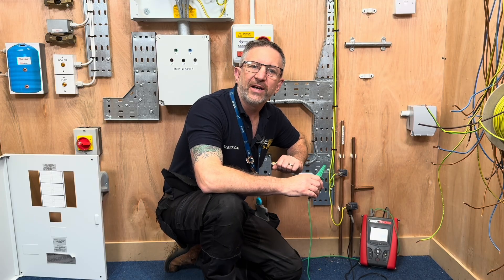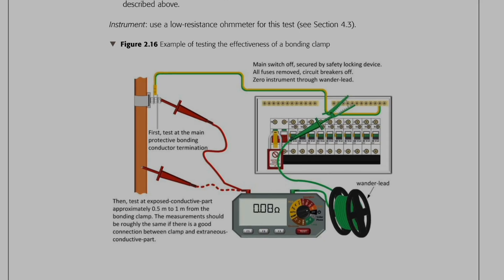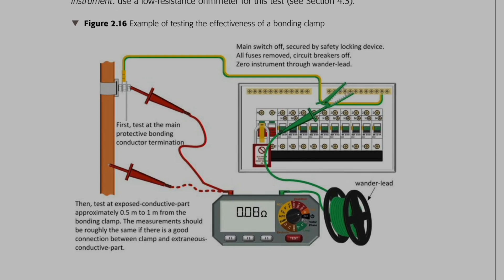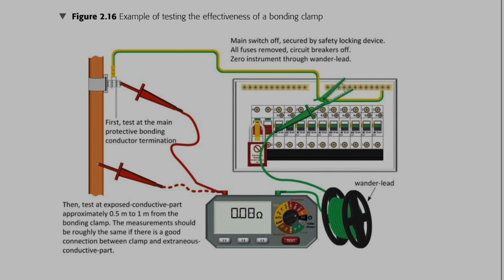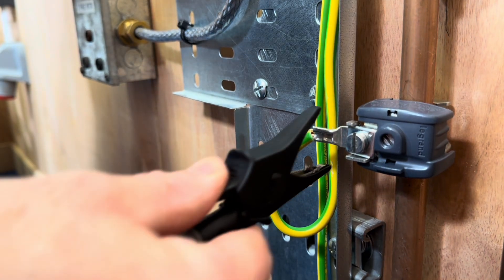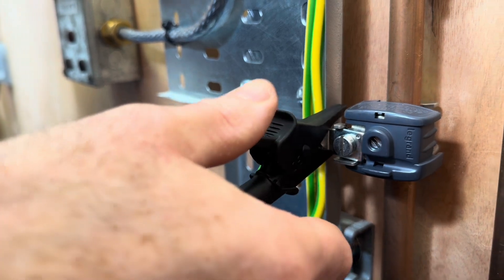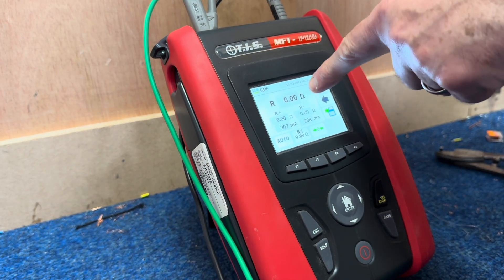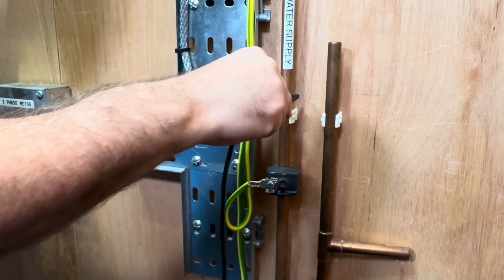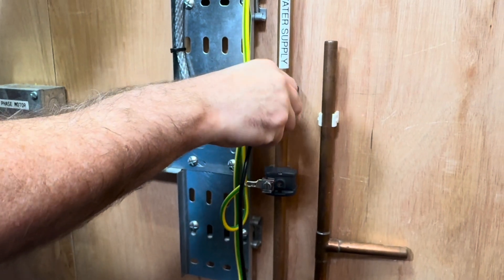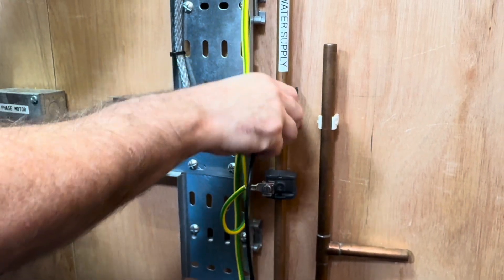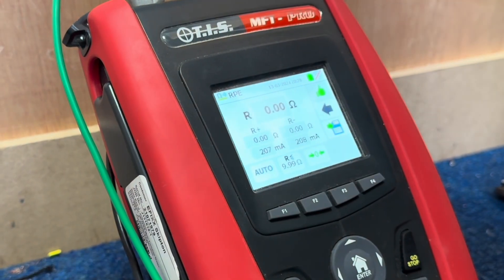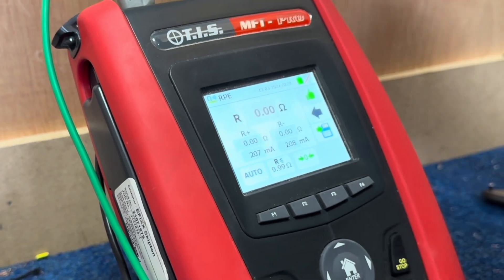We also need to test the effectiveness of a bonding clamp, as shown in figure 2.16 of Guidance Note 3. We test up to the clamp first to verify continuity, then move between 0.5 to a metre away from the clamp. This is to ensure the resistance of the extraneous conductive part is sufficiently low.